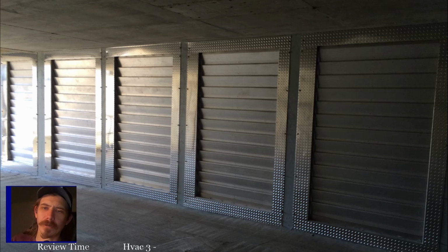And as soon as you see the first failure out of something that's brand new or not of an age at which it should fail, then pay close attention to what factors caused it to fail. It's the same as that old saying, compressors don't fail, they're killed. All right? Compressors do not die, they are murdered. Most parts are murdered in some way. Most parts, if they're used in the situations they're supposed to be used in, will either have a very long service life, or they will perform essentially forever. All right, but there's always that point where it's past, what is it, 1,000,000 cycles or something, 100,000 cycles on a contactor. After that, the contactor's going to fail.